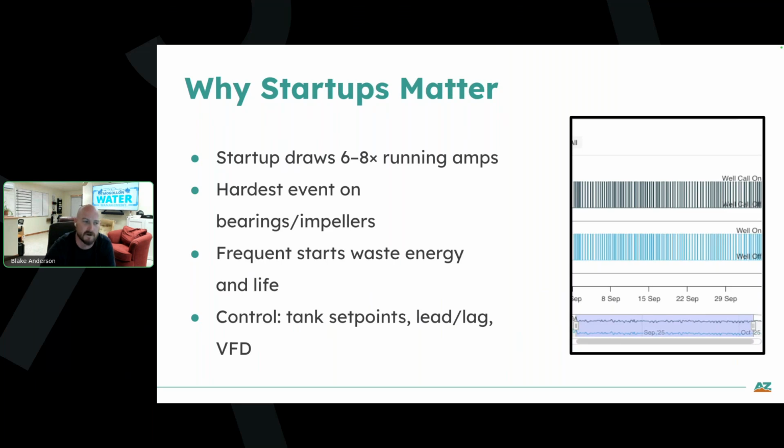And so as an operator, I'll be the first one to admit that when I'm checking wells, I'm really just getting a snapshot of the 10 to 20 minutes that I'm there on that specific day. And if you don't have hour meters or start meters on your panel that you're logging, it can be really hard to tell how often your pumps cycle. And so we just brought on SCADA for a couple of our systems, and one of the sites had a booster in it, and the vendor was nice enough to call me after we got installed and make sure there wasn't some sort of problem with the programming, because the booster had run over 180 times that day.